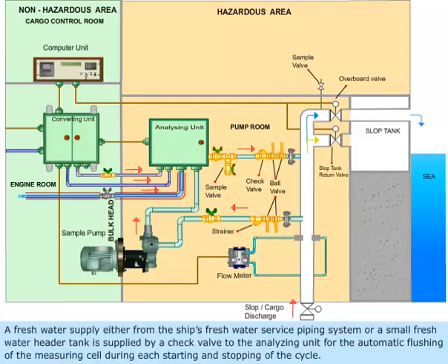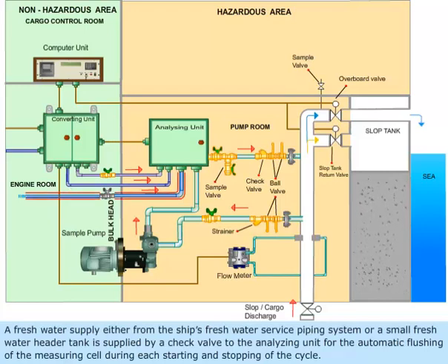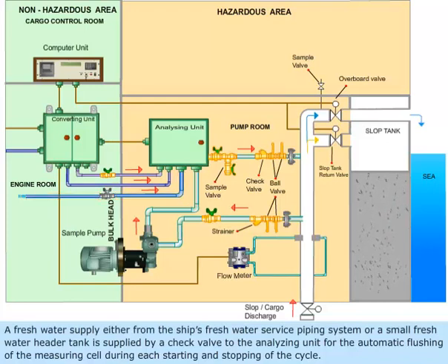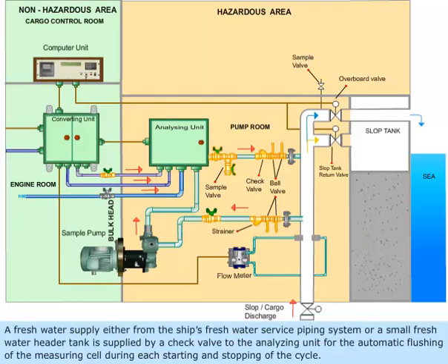Piping for cleaning liquid, flushing water, and cable inlets for the intrinsically safe power supply and measuring signals are also included. A fresh water supply, either from the ship's fresh water service piping system or a small fresh water header tank, is supplied by a check valve to the analyzing unit for the automatic flushing of the measuring cell during each starting and stopping of the cycle.